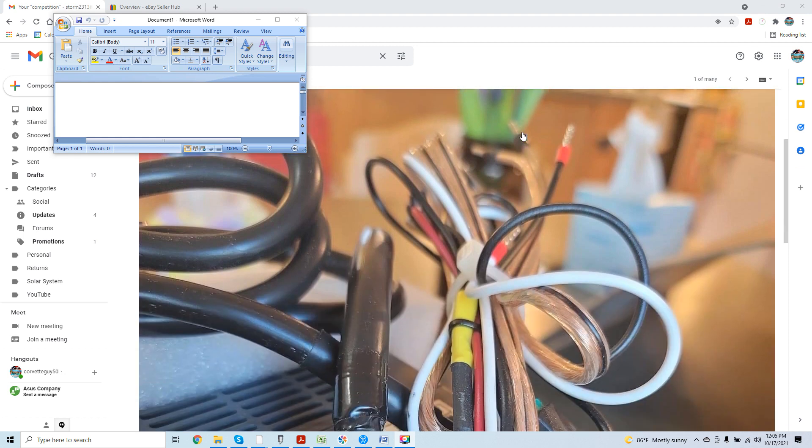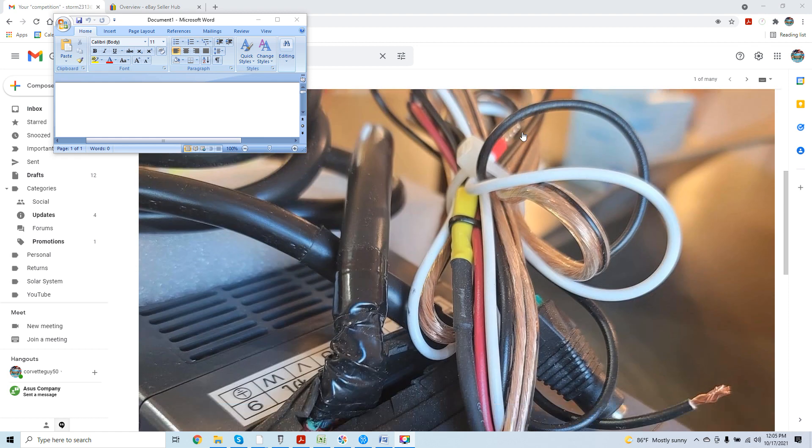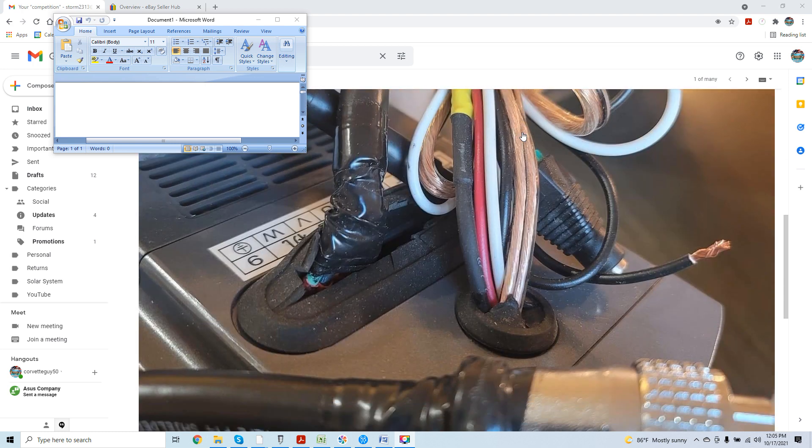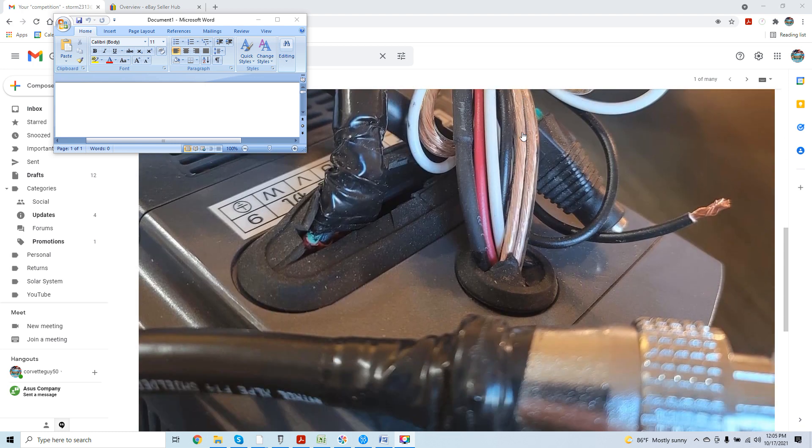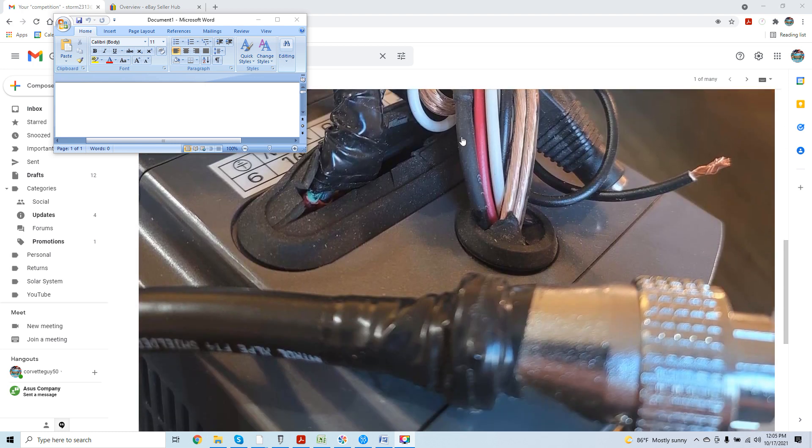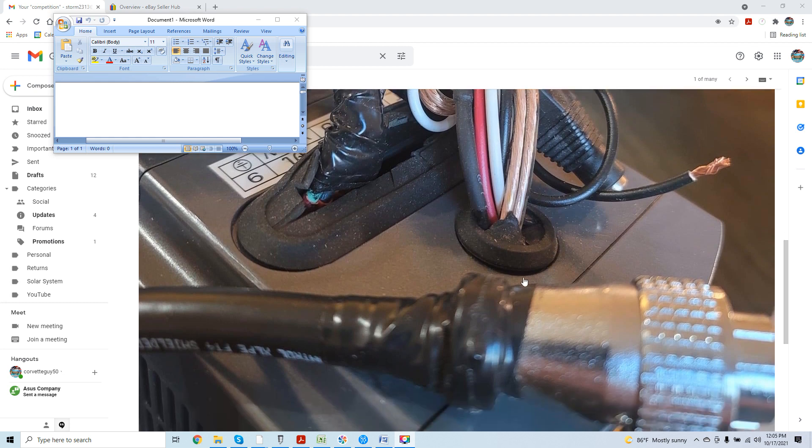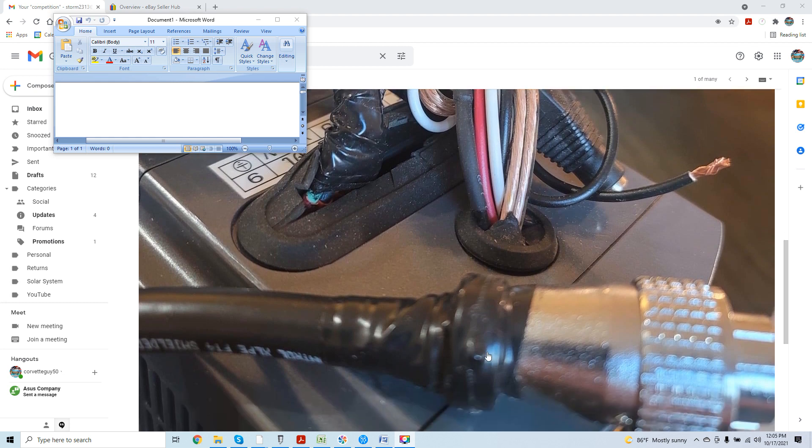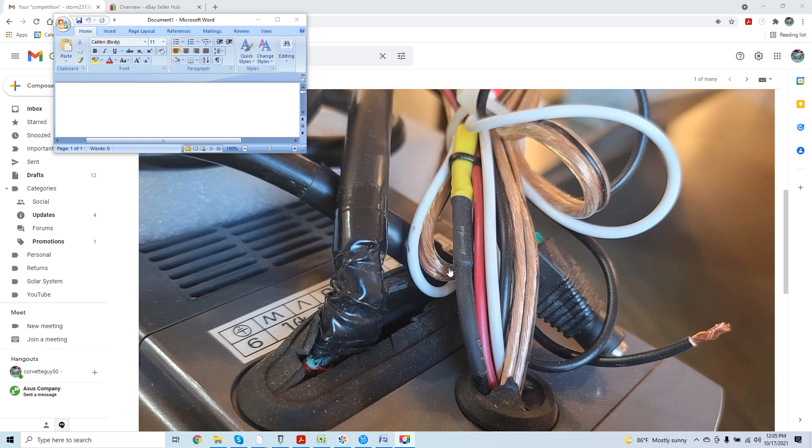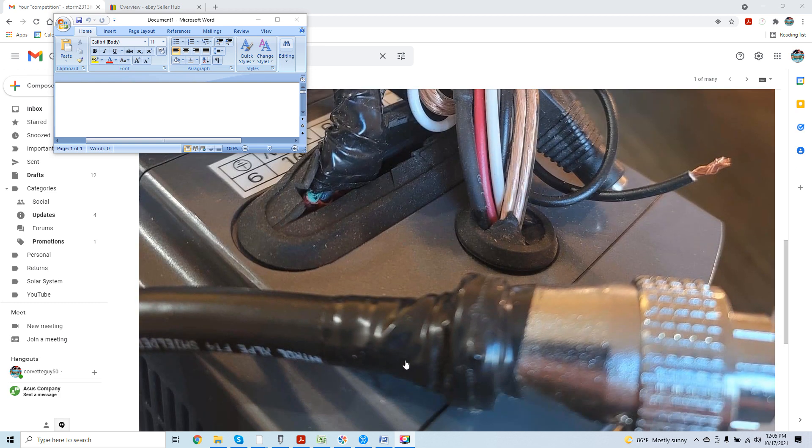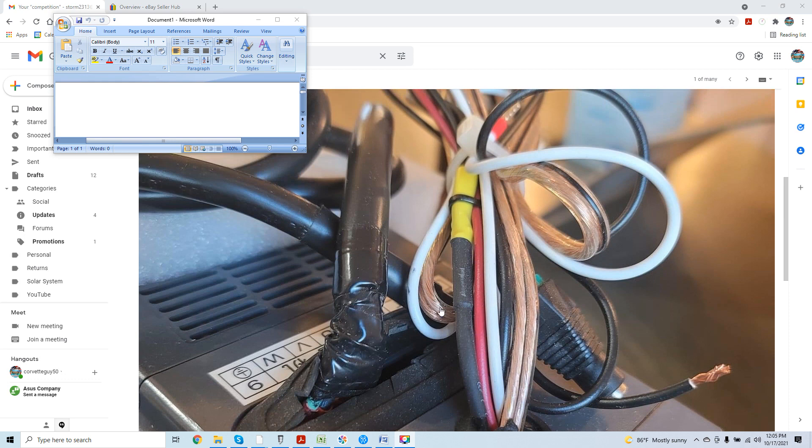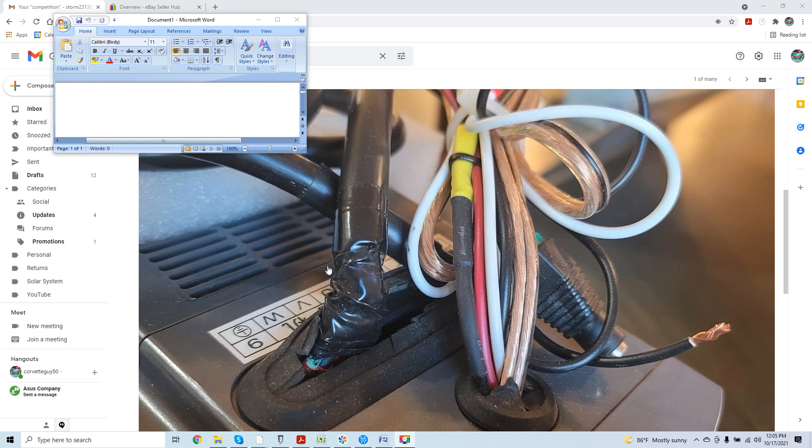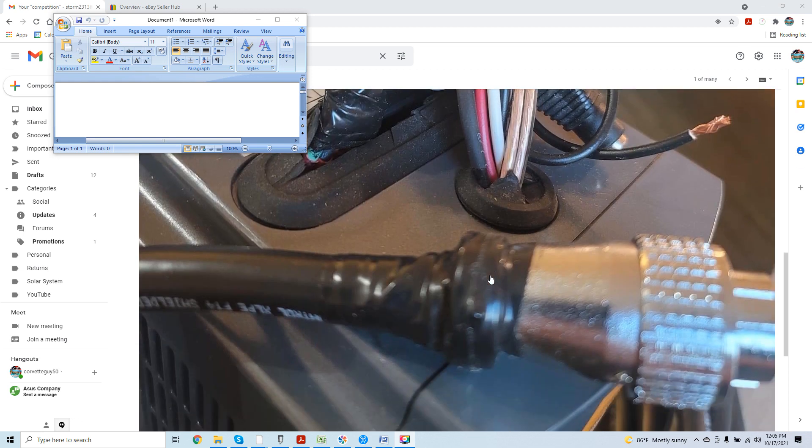I always appreciate continued support from all of you guys. I love that. And anything I can do to help you, I look forward to. But this is terrifying. When I see stuff like this, and many of you who are getting involved with CNC don't realize these are three-phase cables, this is frightening. If you ever receive a cable that looks like this, whether it be one end or both ends, immediately contact the vendor and send it back immediately. I mean, this is treacherous right here.